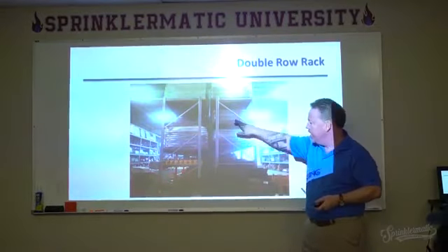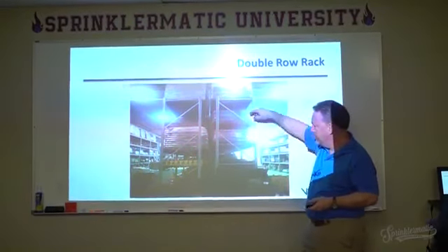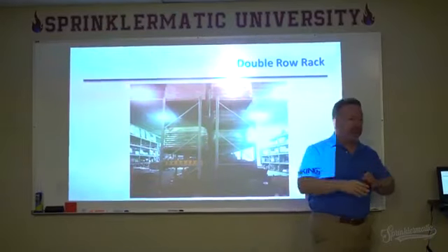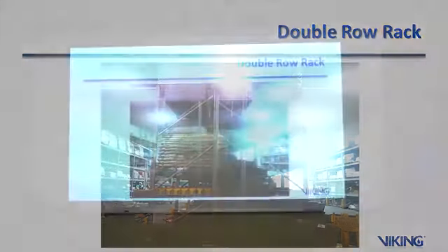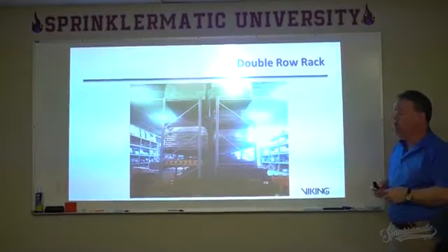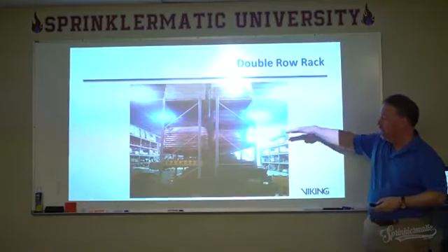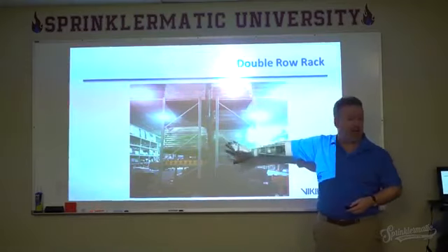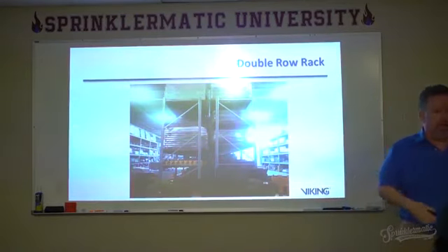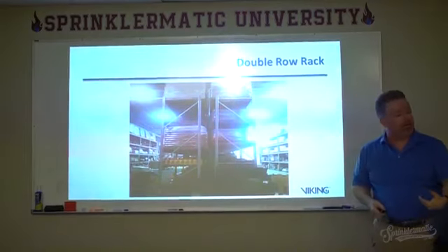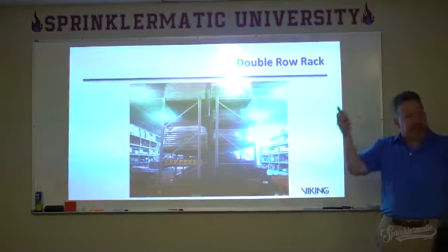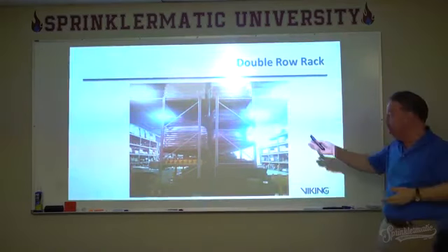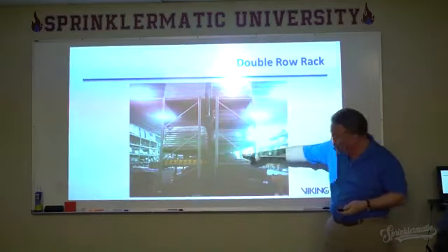Not only do we have air moving around all of this, but we've got air that can move down the flue spaces between the two racks. So there's a lot of capability here, possibilities for that fire to grow. Also, because it's so large and because these are pretty solid units, it's a bigger challenge to get water down through them.